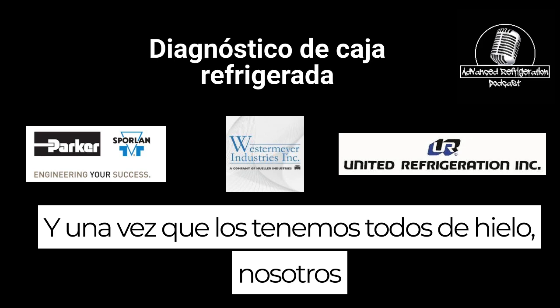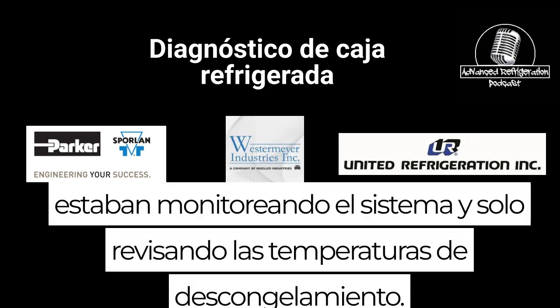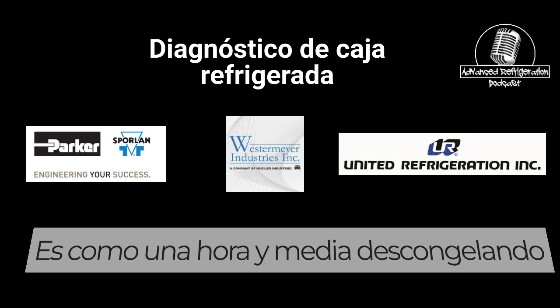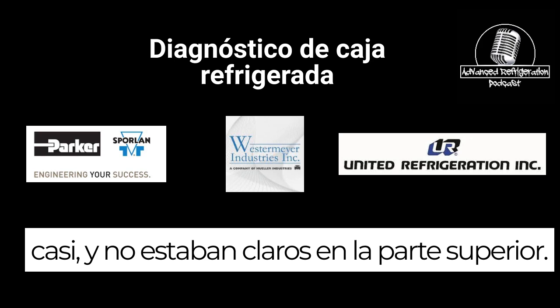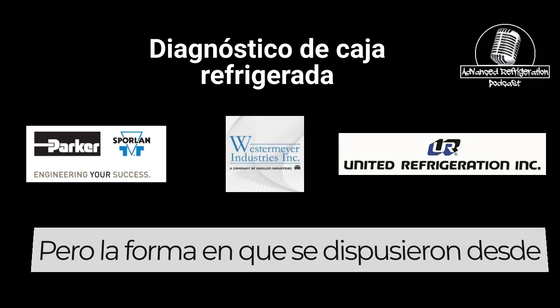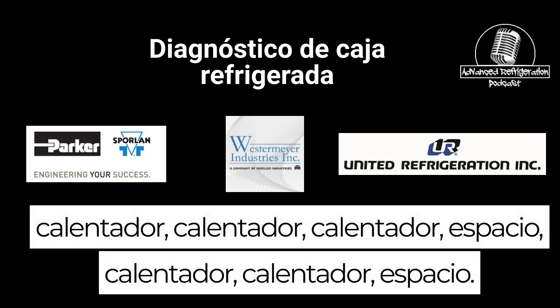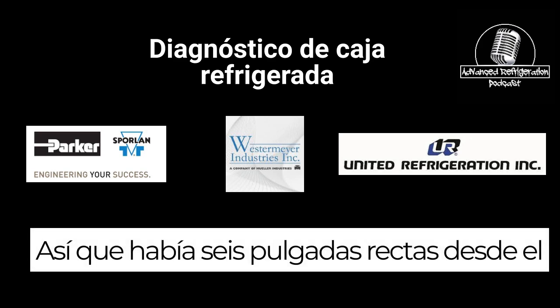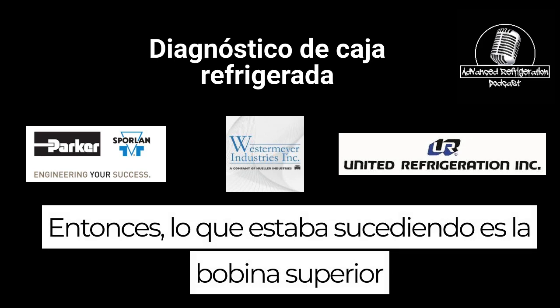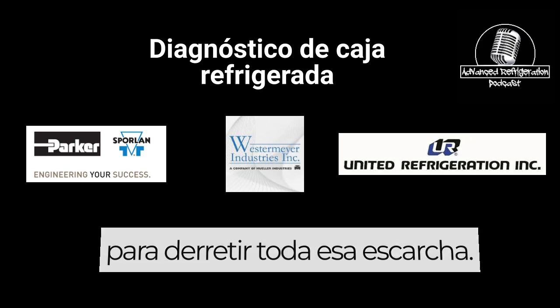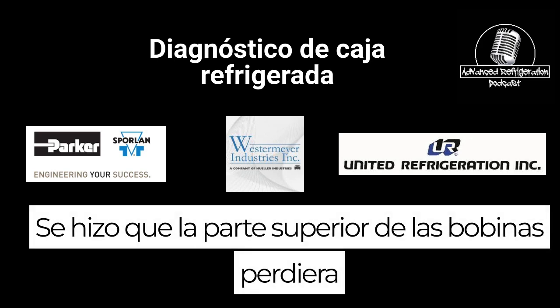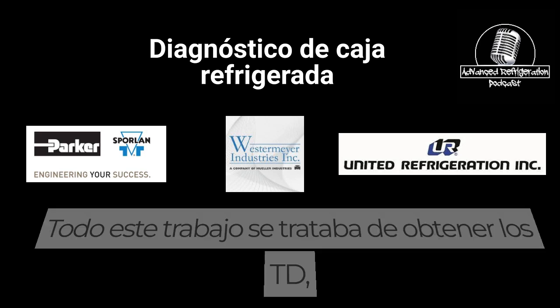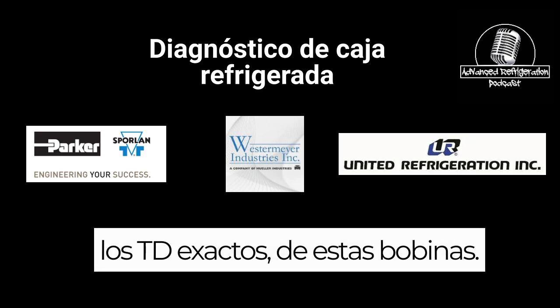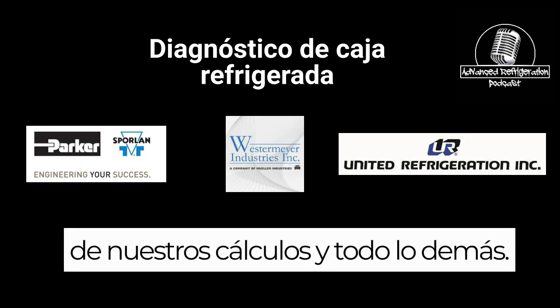And once we got them all de-iced, we were monitoring the system and just checking defrost temps. And I had these coils up to like an hour and a half defrost almost, and they weren't clearing the tops. So I figured we were missing a heater, the way they were laid out. From the bottom of the coil, it went heater, heater, heater, heater, heater, heater, space, heater, heater, space, space, space. So there was a straight 6 inches from the top of the coil to the next heater. So what was happening is the top of the coil wouldn't get warm enough during a defrost period to melt all that frost off. It caused the tops of the coils to lose airflow, and it was affecting the TDs on our coils. This whole job was about getting the exact TDs out of these coils. So it was throwing off all of our calculations and everything else.